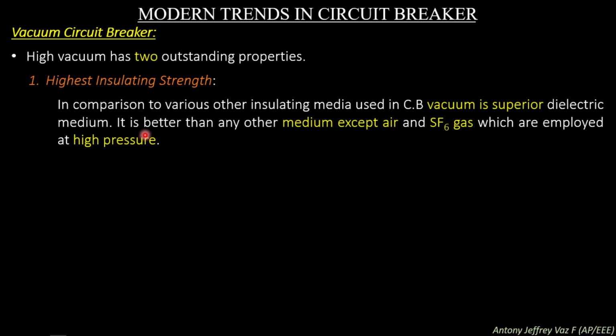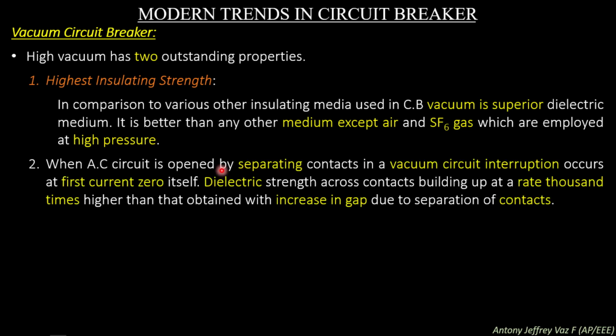It is better than any other medium except air and SF6 gas which are employed at high pressure. So when air and SF6 gas are used at high pressure, they will have very good characteristics. When an AC circuit is opened by separating contacts in a vacuum circuit breaker, interruption occurs at the first current zero itself. Dielectric strength across the contacts builds up at a rate 1000 times higher than that obtained with increase in gap due to separation of contacts.